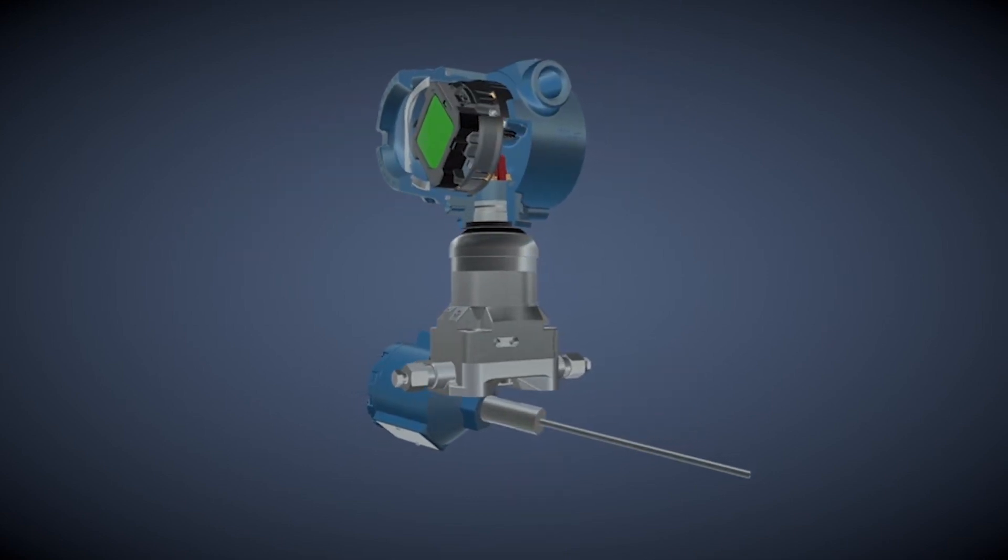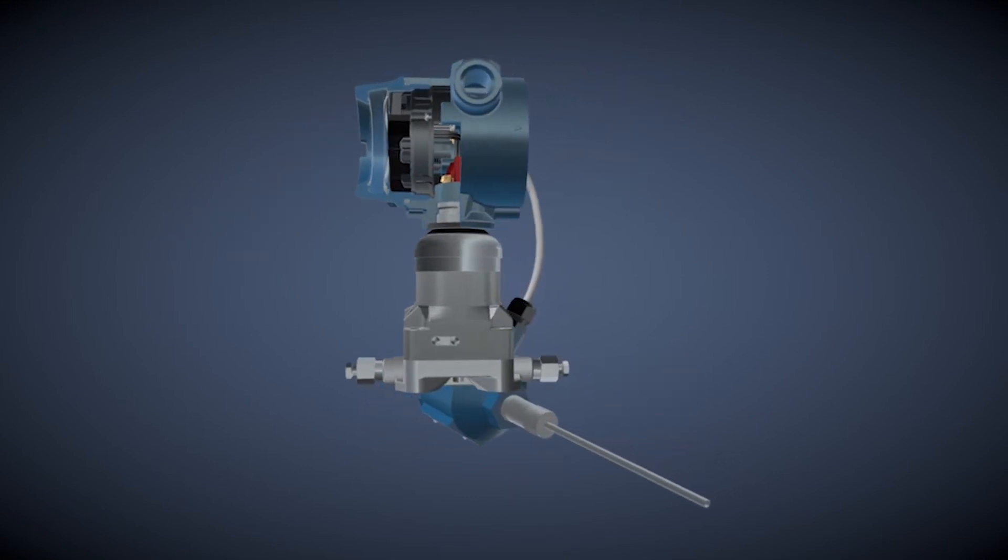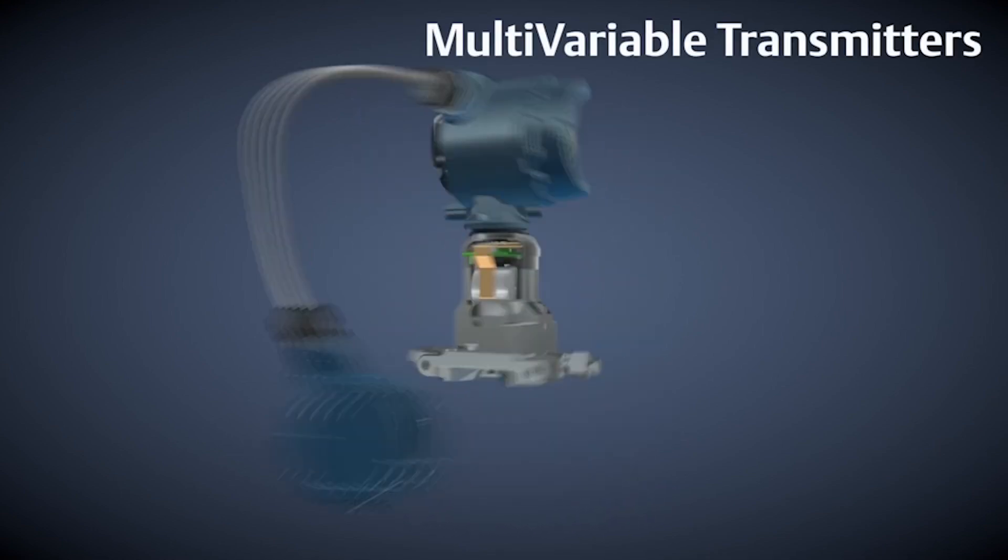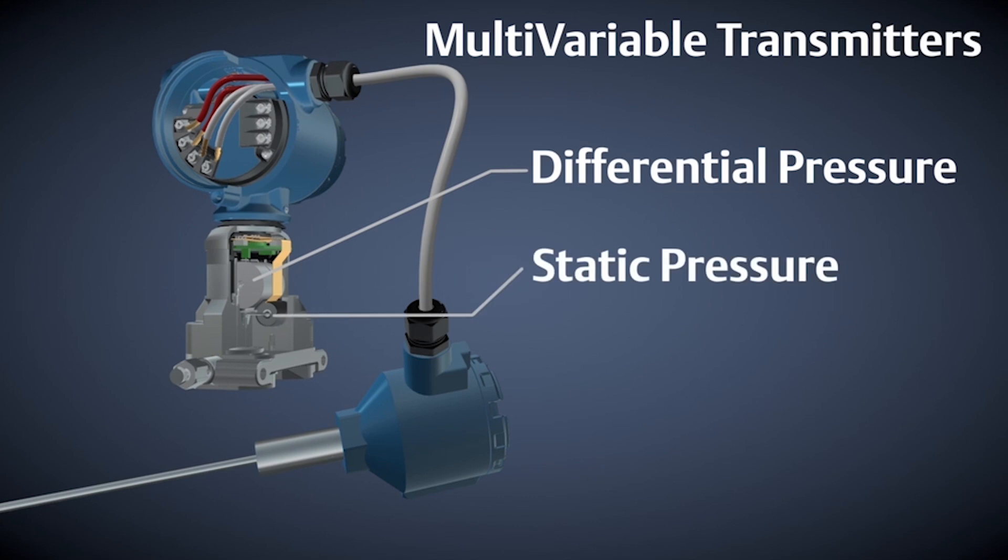There have also been major flow transmitter advancements with the arrival of multivariable technology. Multivariable transmitters measure differential pressure, static pressure, and process temperature, resulting in a highly accurate mass or energy flow measurement.